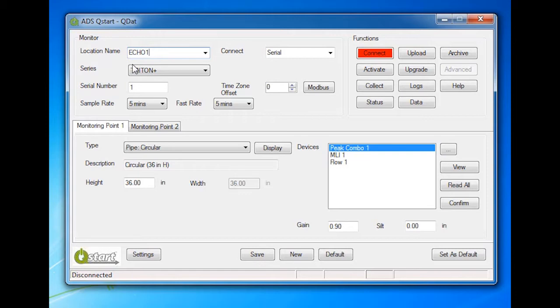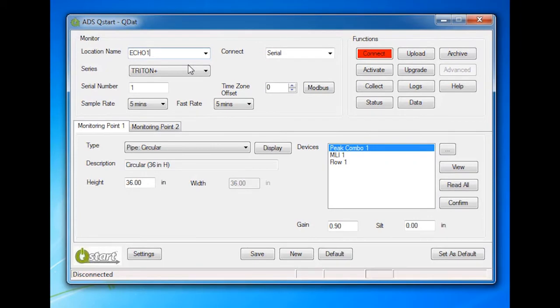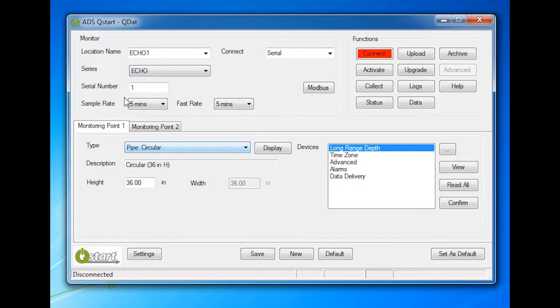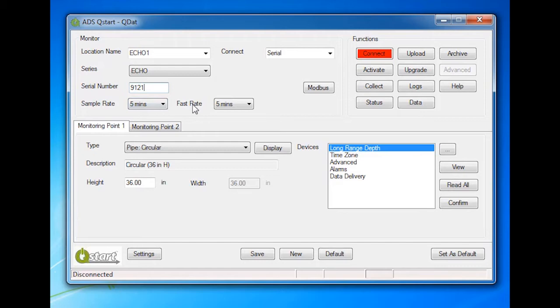Also, do not duplicate more than the first 7 characters of another location's name unless the 8th or later character is followed by an underscore and a unique character. Select Echo for the series type and enter the serial number. Leave the default values for the sample rate as 5 minutes and the fast rate as 5 minutes unless you desire a faster sampling rate during alarm conditions.